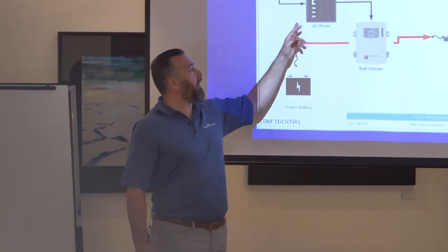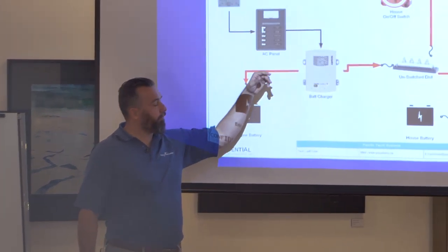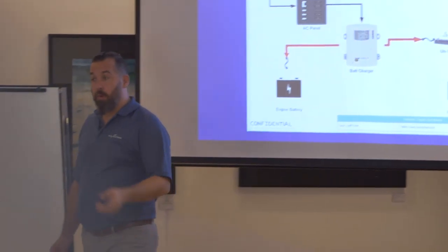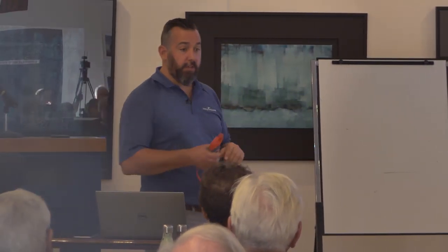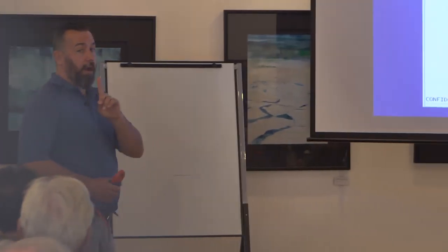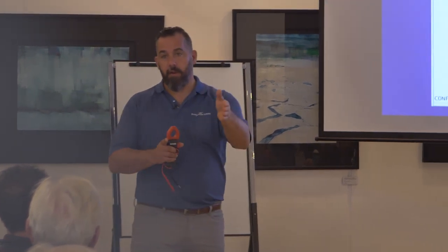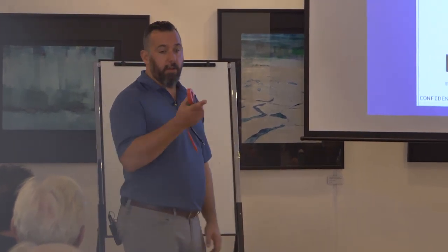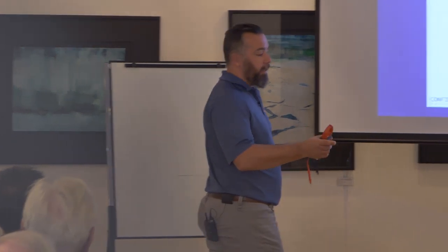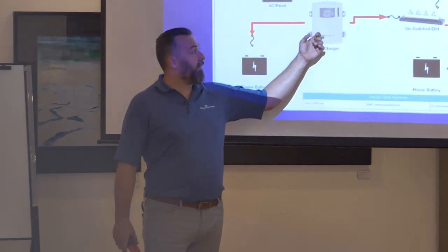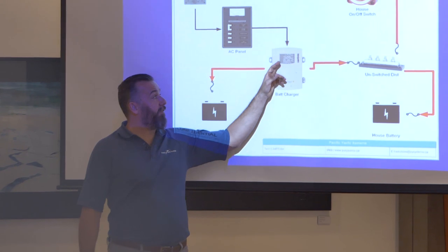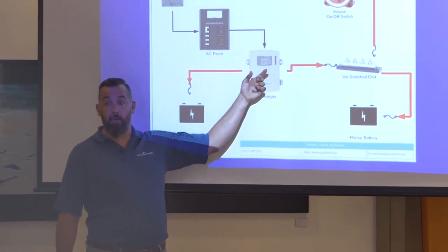The generator is going to have literally a circuit breaker. It might have tripped. Press that. After that, make sure this source selector, and by the way, they get old and then they fail. That could be the issue. So, when you're troubleshooting, you're like, do I have power in my AC panel? Is nothing working on my AC panel? Or just my charger not working on my AC panel? So, process of elimination. If only your charger's not working, try to trip that breaker.